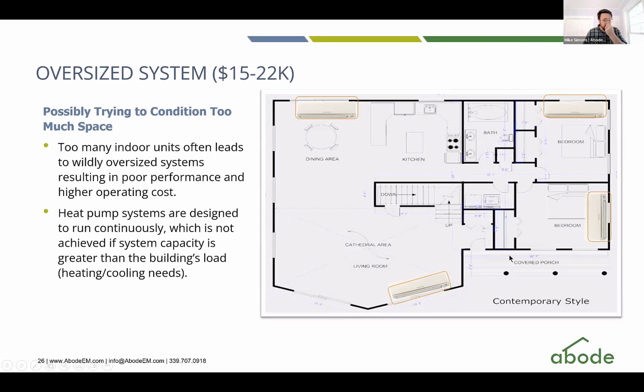So what could happen if you put a ductless unit everywhere where you had a register in each and every room is that it is going to be oversized for the home, even when it's running at its lowest capacity. And that means instead of having a coefficient of performance closer to 3, it'd be closer to 2. So it has a big impact on performance and can also have a big impact on its ability to remove moisture.